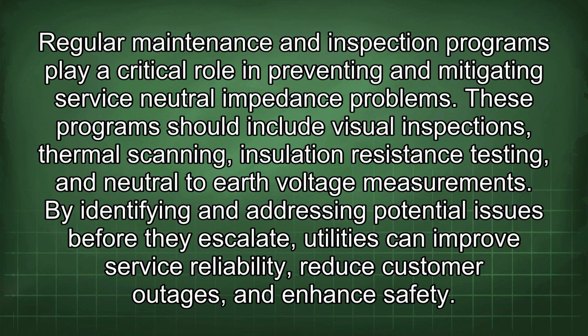Regular maintenance and inspection programs play a critical role in preventing and mitigating service-neutral impedance problems. These programs should include visual inspections, thermal scanning, insulation resistance testing, and neutral-to-earth voltage measurements. By identifying and addressing potential issues before they escalate, utilities can improve service reliability, reduce customer outages, and enhance safety.